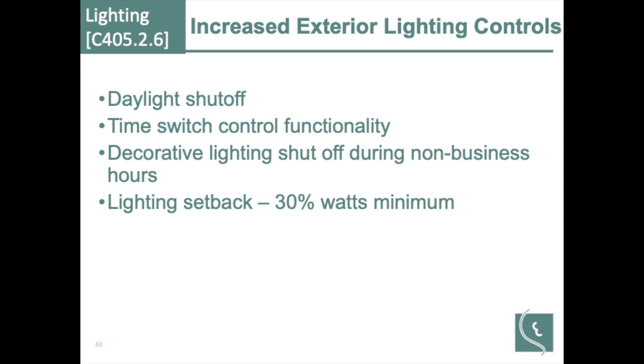Increased exterior lighting controls. Daylight shutoff, something that's been common on lighting for a while. Time switch control functionality. Decorative lighting shutoff during non-business hours was not part of the code previously. It's now part of the code. And lighting setbacks, like parking lot lighting, if there's an occupancy sensor out there to dim the lights down if no one's driving in the parking lot, it's now part of the code. Previously, it was either daylight harvesting or time clock control for exterior lighting. Now it has to have both.